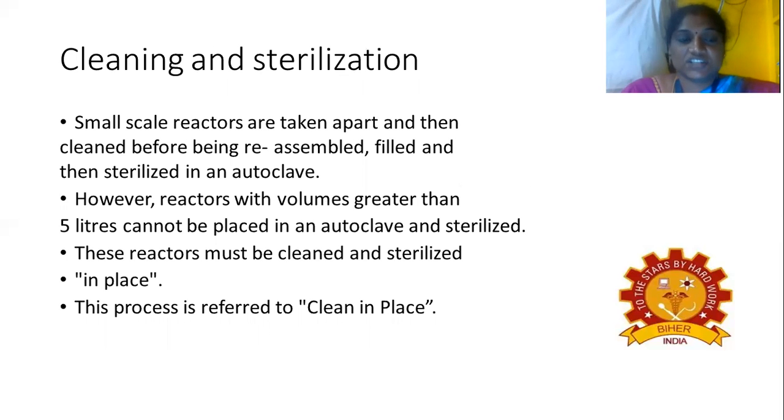Cleaning and sterilization. Small scale reactors are taken apart and cleaned before being reassembled, filled, and then sterilized in an autoclave. So it is possible with small sized reactors, but it is difficult for large scale reactors. Reactors with volumes greater than 5 liters cannot be placed in an autoclave and sterilized. So these reactors must be cleaned and sterilized in place. This process is referred to as clean in place.